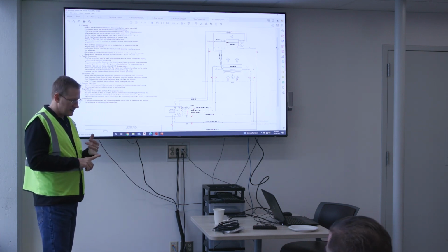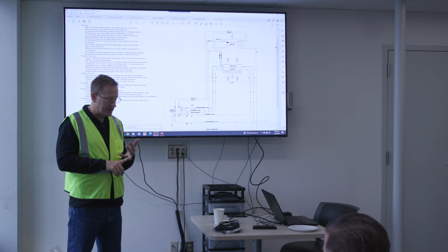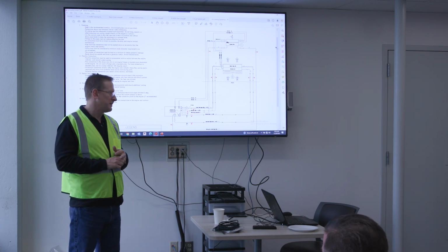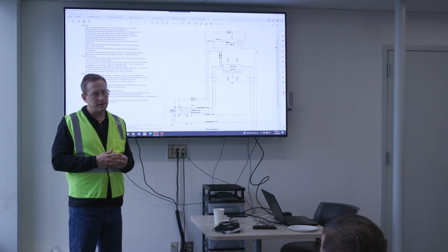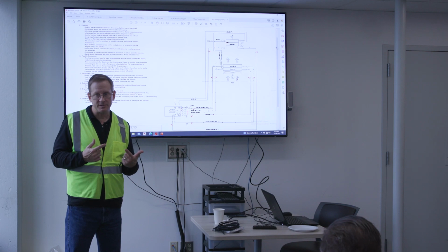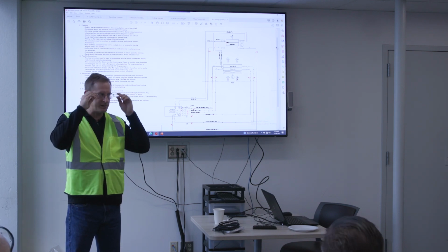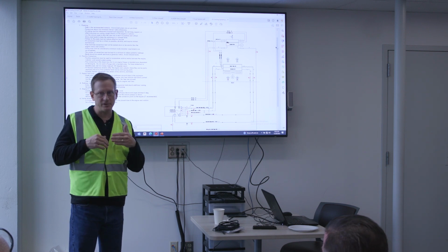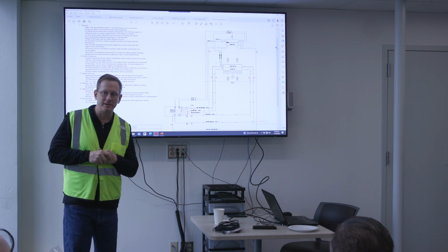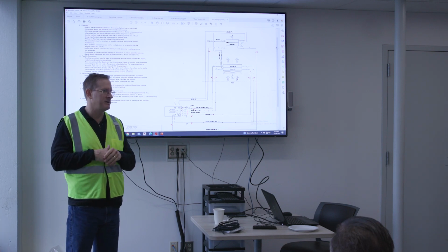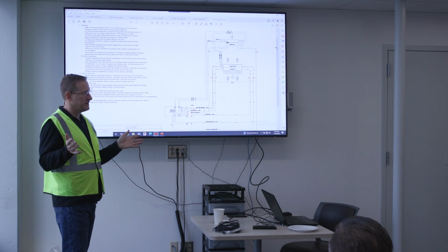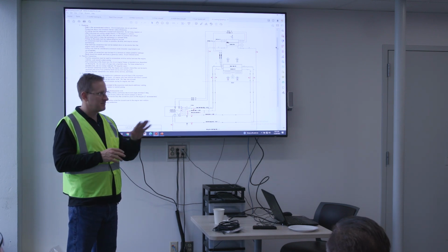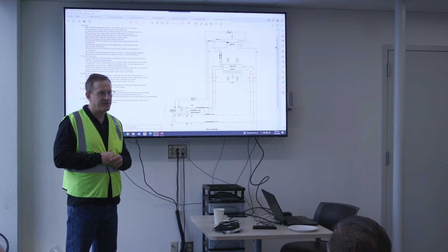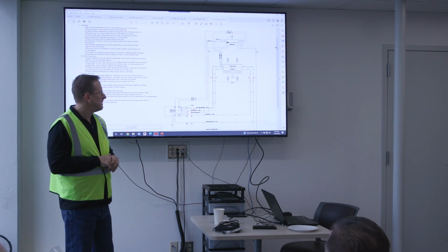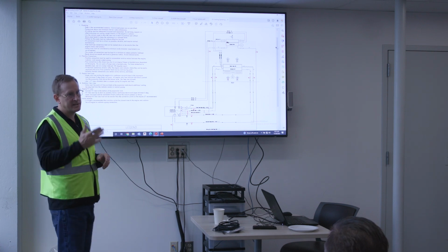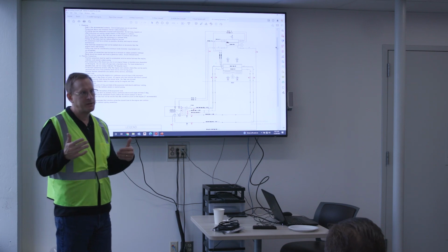There is also a room temperature input that we take from a thermostat, so that we can alarm if the room temperature gets too high. Right now we are getting that alarm, and that's because the thermostat is set too low. So at some point, McKinstry is going to have to go in and raise that threshold because it's alarming at a much lower temperature than it should be. Which I'm not even sure what it's set at, because there's a quality assurance sticker that covers the setting of the thermostat, so we didn't want to touch that. But it needs to be set higher to get rid of that alarm. Okay, so that's why you saw the high room temp alarm on the UCP.